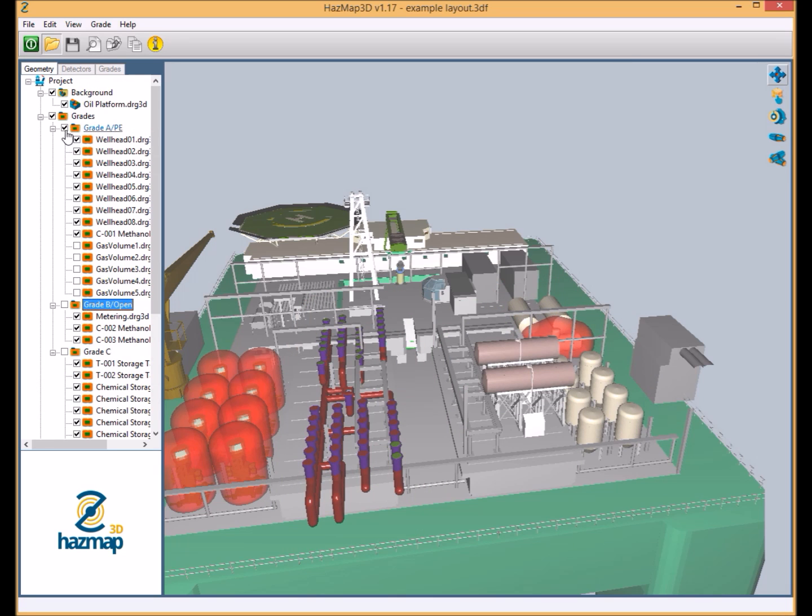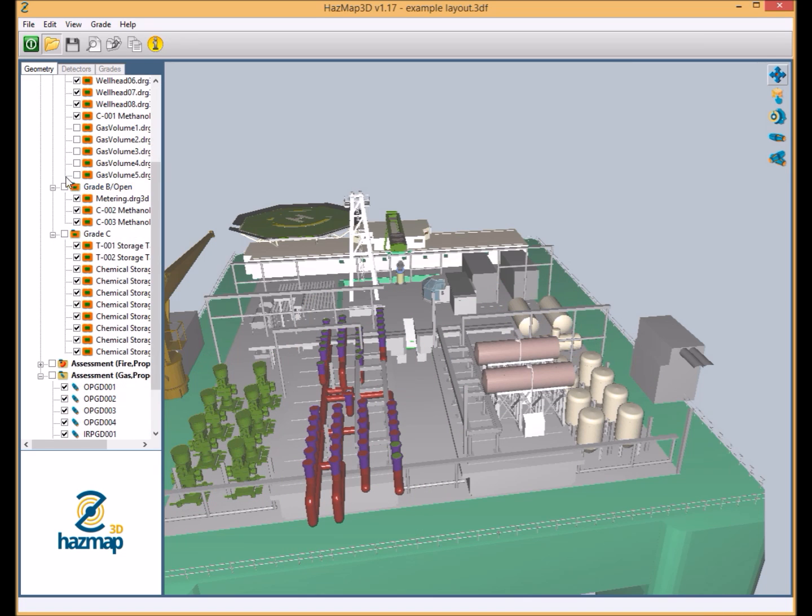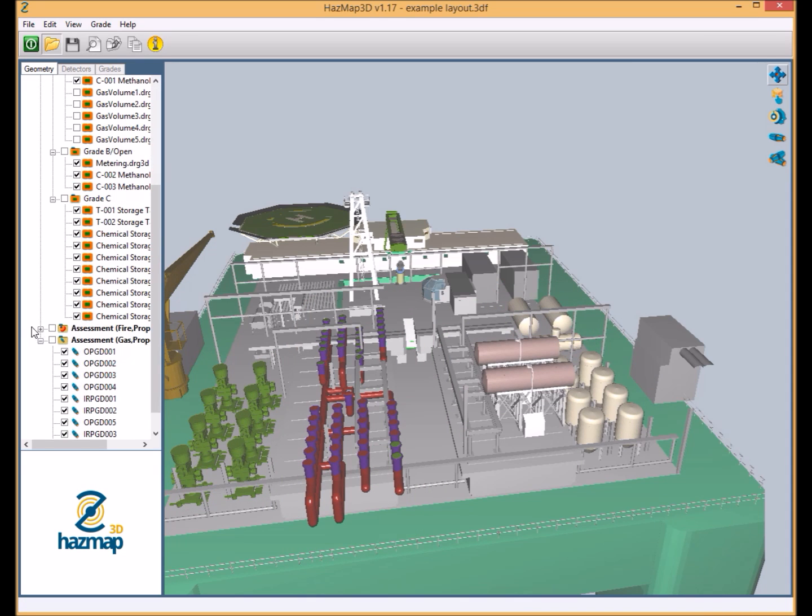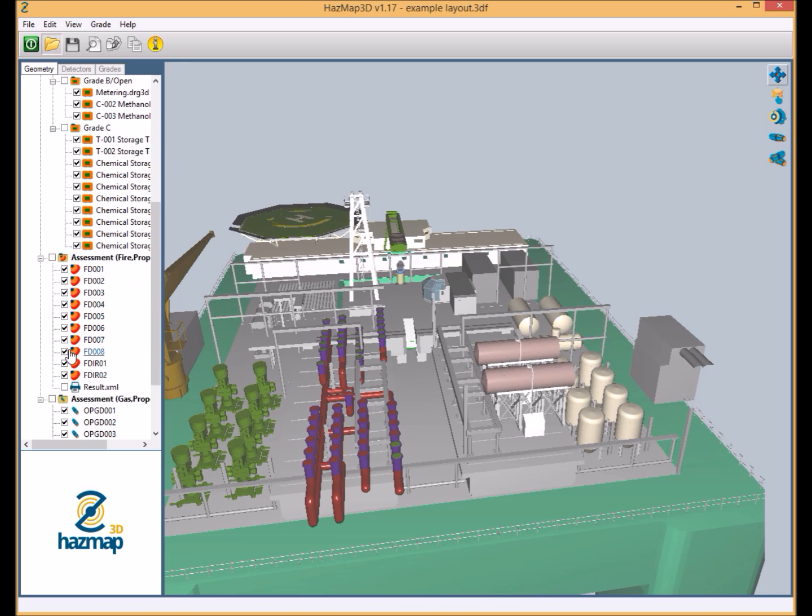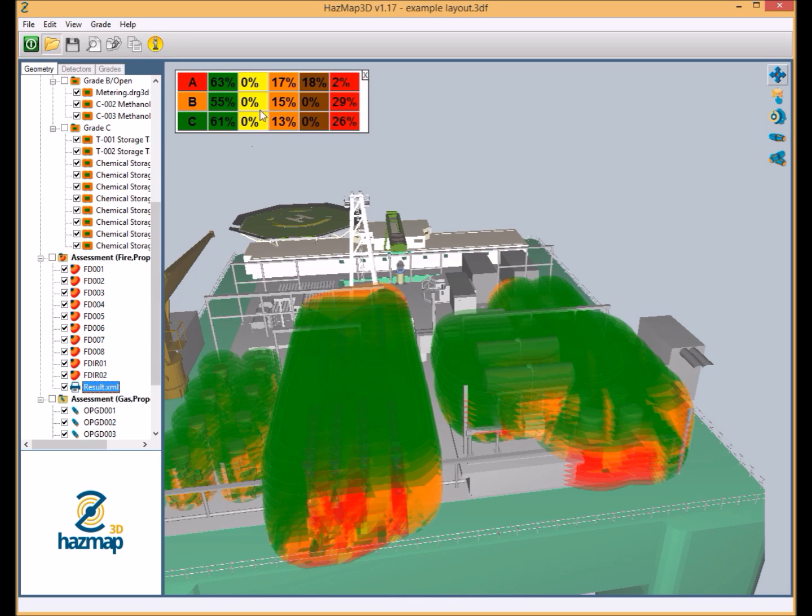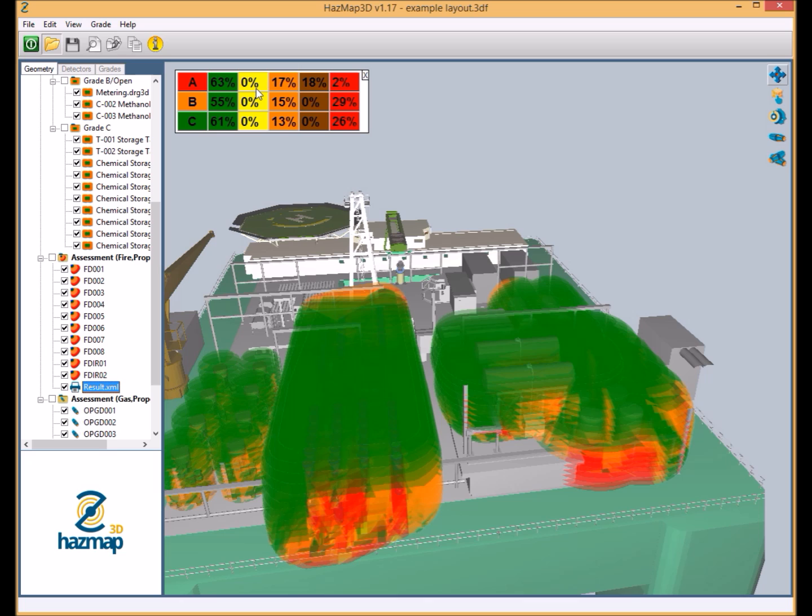In the assessment, we can obviously see some additional grades or additional coverage percentages with yellow. Obviously there are none present in this particular assessment, and also brown. Now what these stand for, these are very specific to individual methodologies, where you could perhaps not detect your smaller fast response alarm target fire size, but when it grows to a stage where you have an acceptable control action target fire size, you would get a 2 out of n voted coverage.